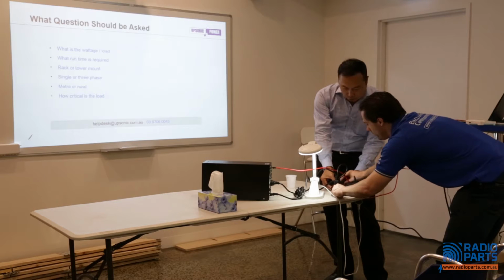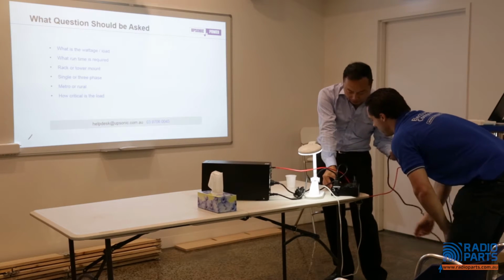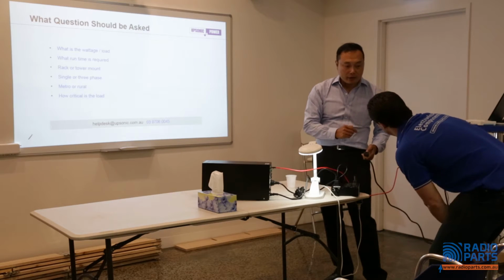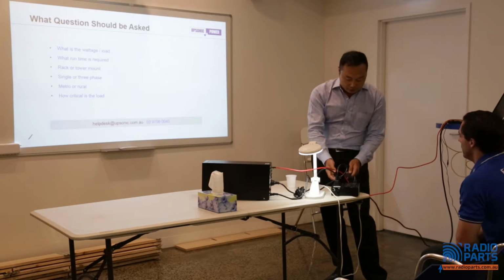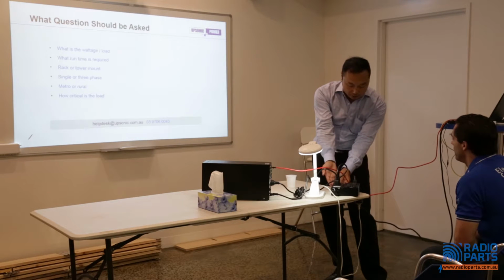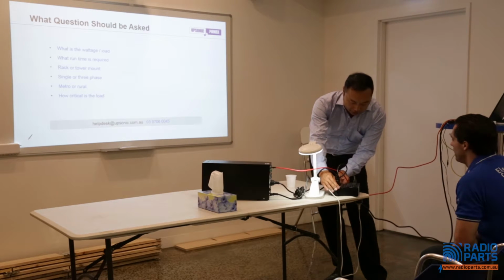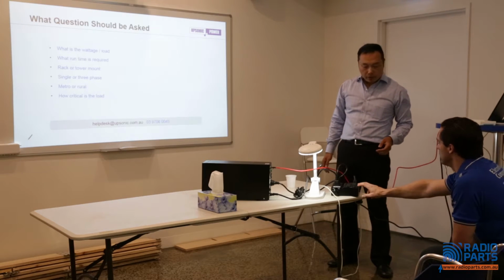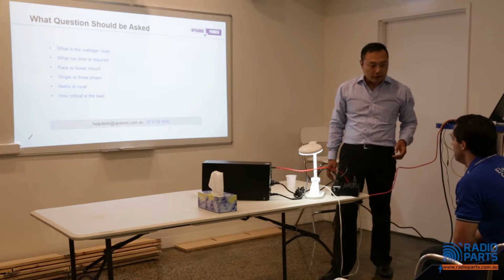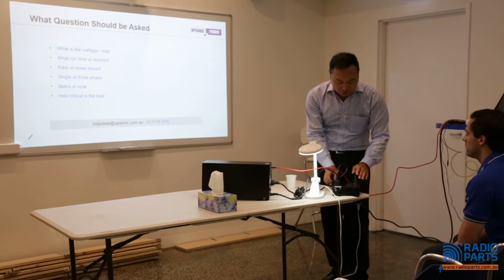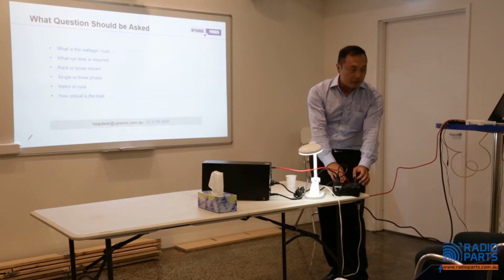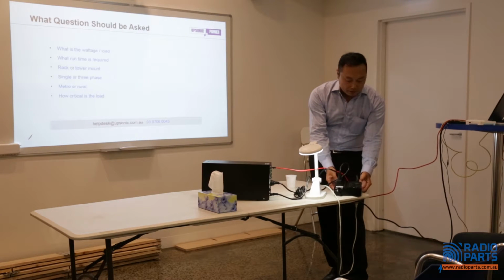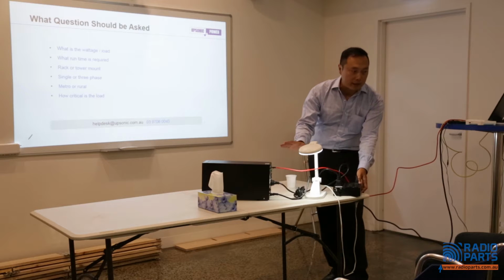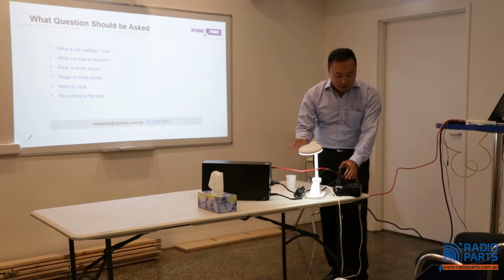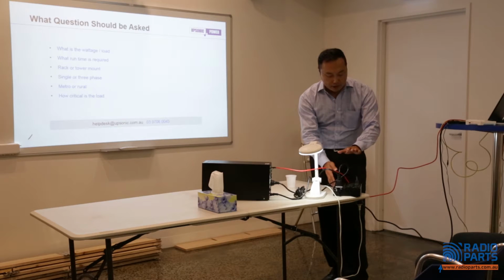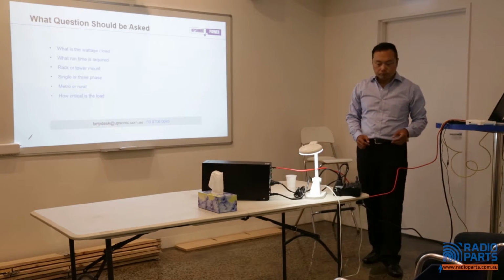We go into normal mode, backed up by UPS, and you can pull it out, unplug it, and then put in a different one to measure the current, so there's no downtime. Insert a power meter here, that's a good way to check the load also, without any downtime. It's pretty good, and it's not expensive, around $200 to $300 for this. This maintenance bypass switch is compatible with UPS up to 3 kVA. Above 3 kVA, we need a higher-end model. It's pretty good actually.